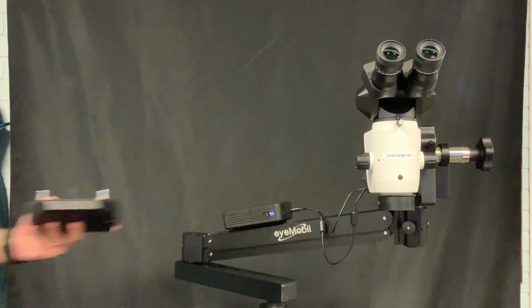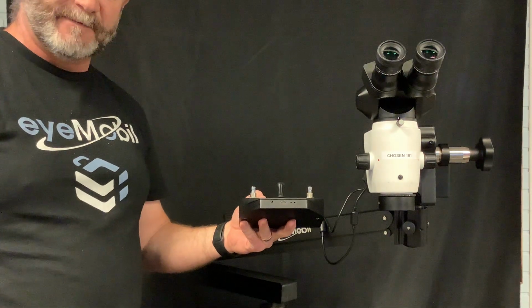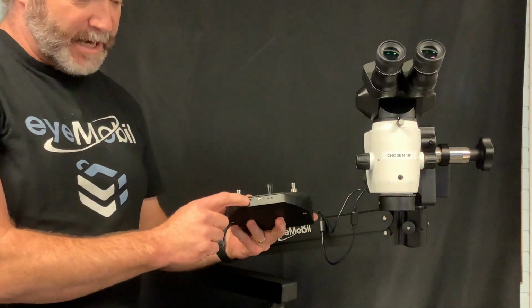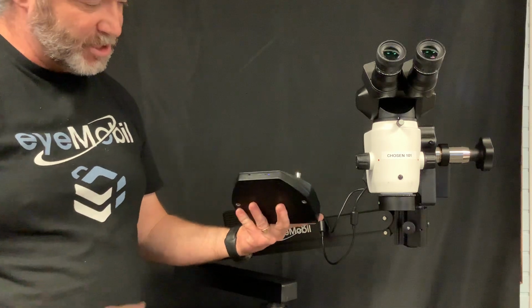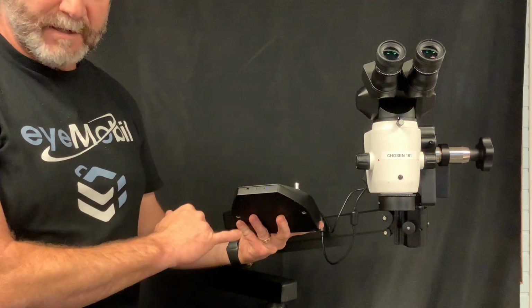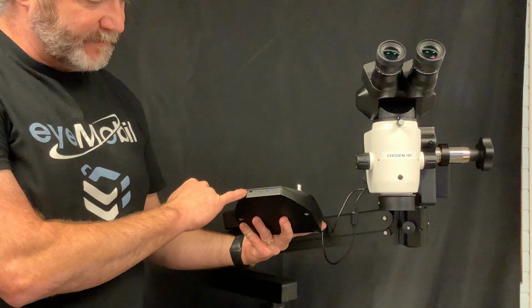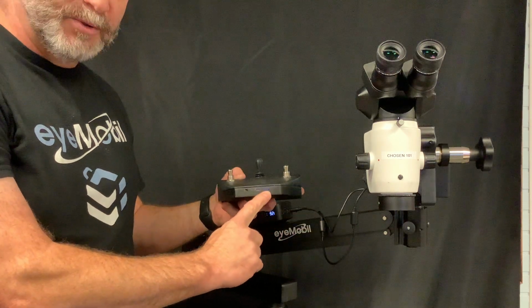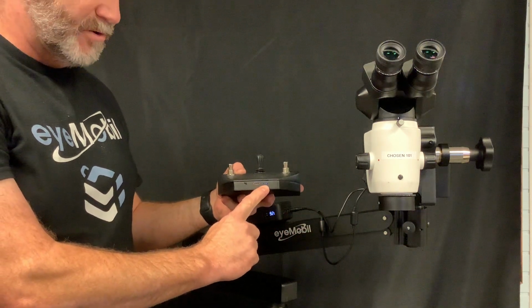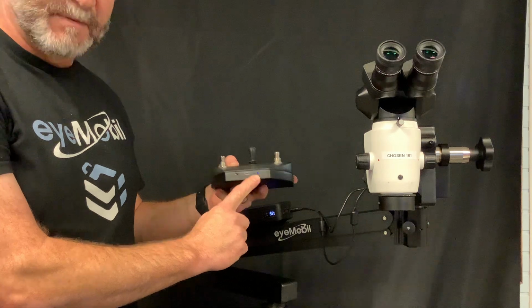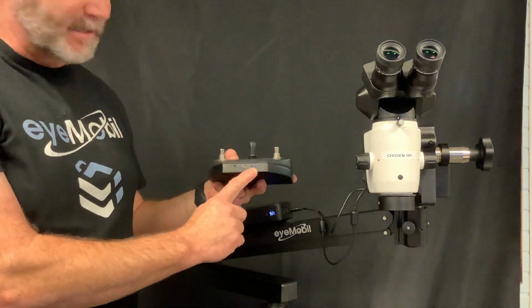You'll then need to remove the XY foot pedal from the case and turn the switch to the right, which is marked as on with a single line versus off for the 0. You'll see a blue light indicating that the unit is on. If the blue light is not on, then the battery has likely died.